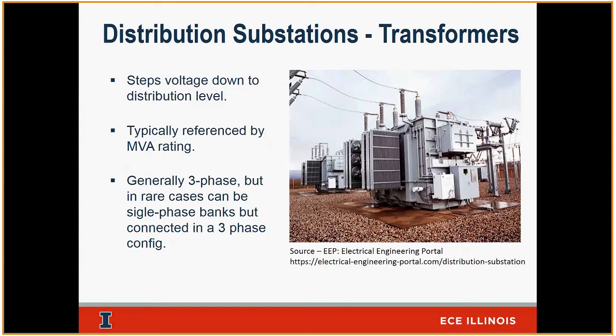I talked already about the transformers, right? One more thing about these transformers, they are typically three-phase. It's very rare to see single-phase transformers inside a substation of this size. If they're single-phase, they're probably connected in a three-phase fashion. But to my knowledge, I'd say 99% of transformers in the Ameren territory are all three-phase transformers. Like I said, they're based on MVA rating. That's how we rate our transformers, and we speak about transformers in the MVA language.